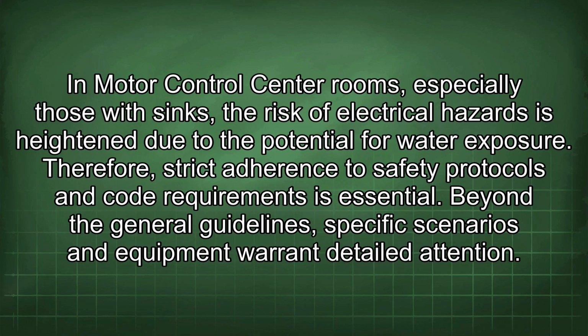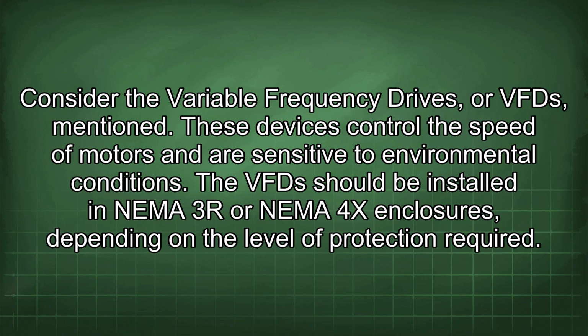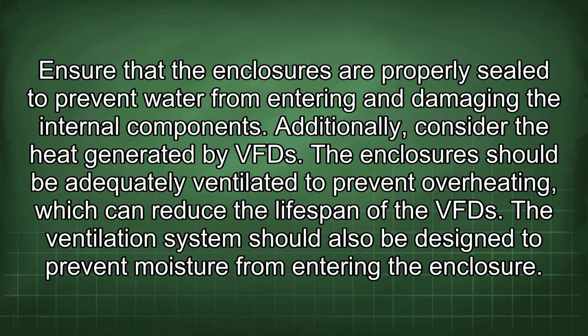Beyond the general guidelines, specific scenarios and equipment warrant detailed attention. Consider the variable frequency drives, or VFDs, mentioned. These devices control the speed of motors and are sensitive to environmental conditions. The VFD should be installed in NEMA 3R or NEMA 4X enclosures depending on the level of protection required. Ensure that the enclosures are properly sealed to prevent water from entering and damaging the internal components.